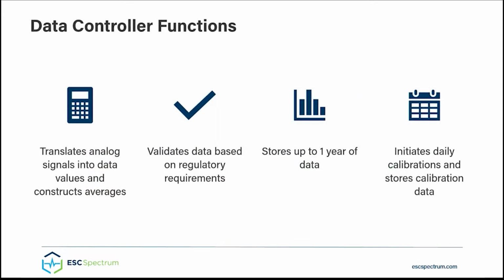The controller translates the analyzer signals into concentration values, typically parts per million or ppm. It then constructs the averaging intervals required under a plant's air permit, typically 15 minute, 1 hour, and so on, and these may be block or rolling averages. The controller validates the data as good or bad. Only good data can be used for regulatory reporting. Bad data can result from failed calibrations, downtime, and insufficient amount of data within a required interval of time, to name a few. The controller can store up to 1 year of data and provides redundancy to the DAS server.